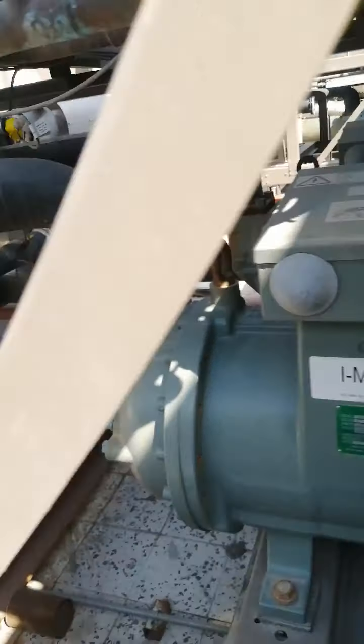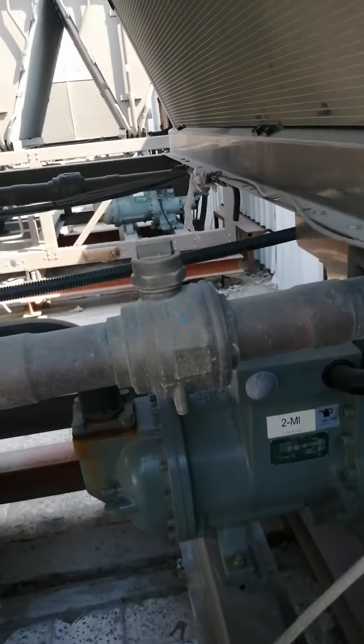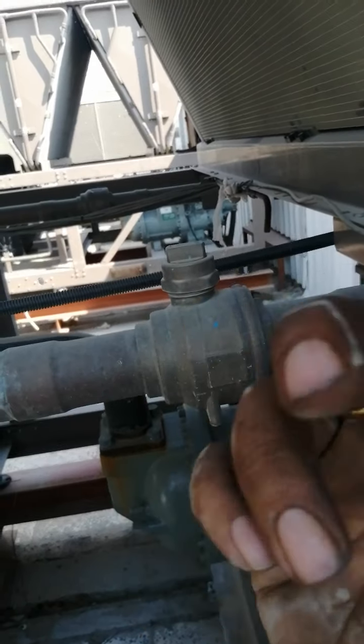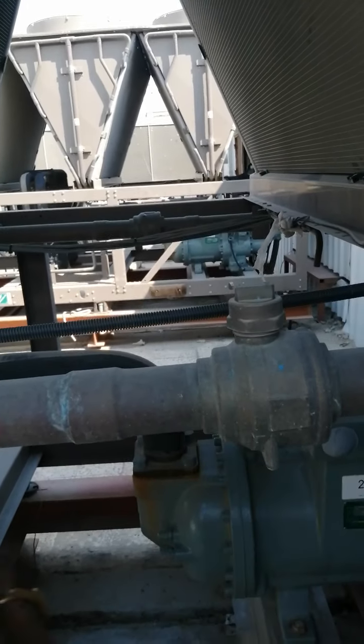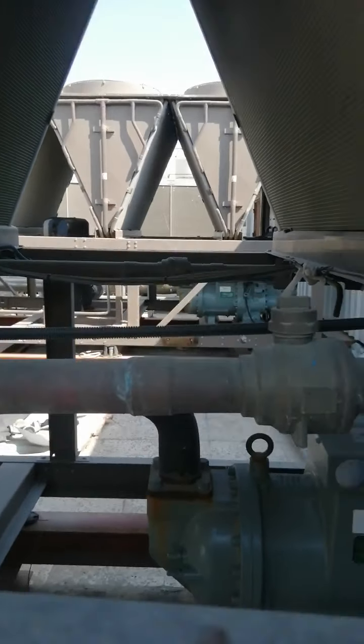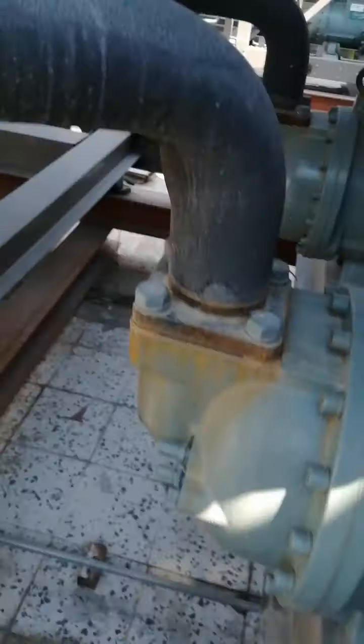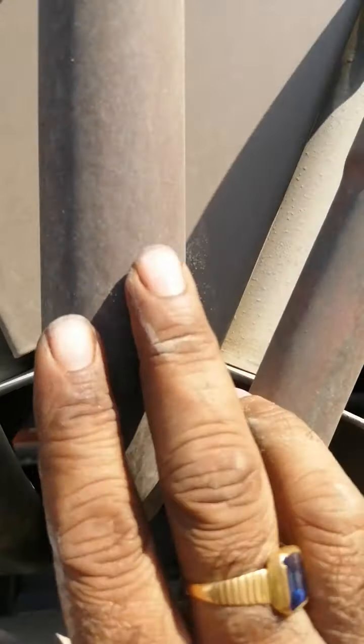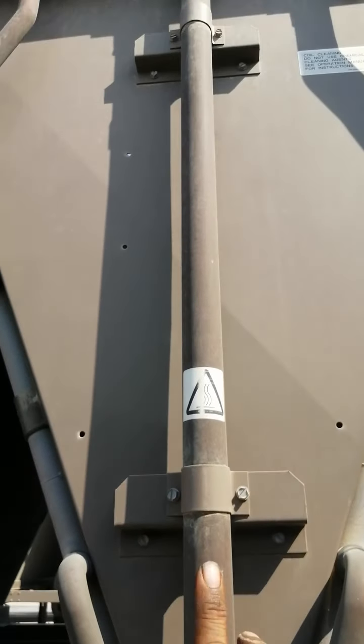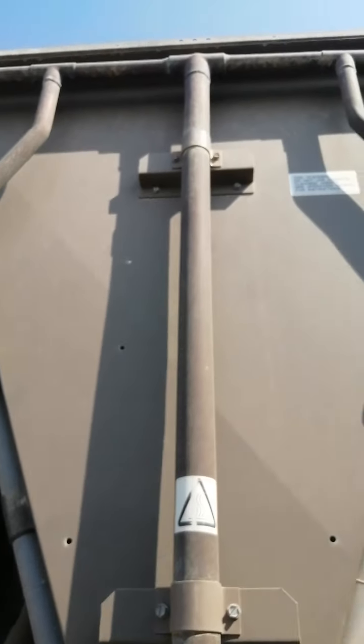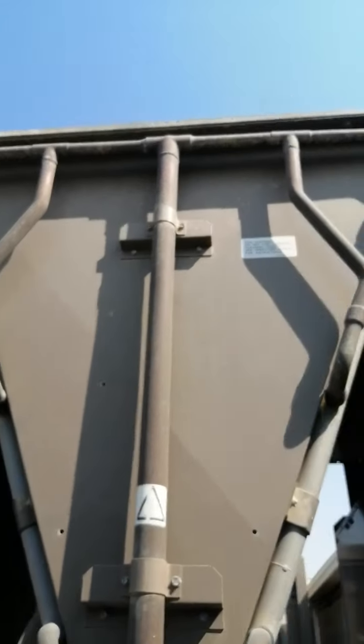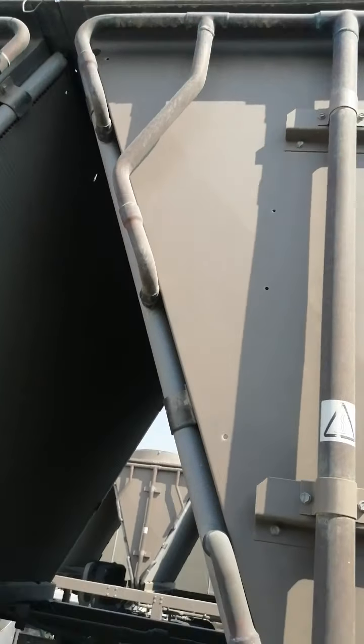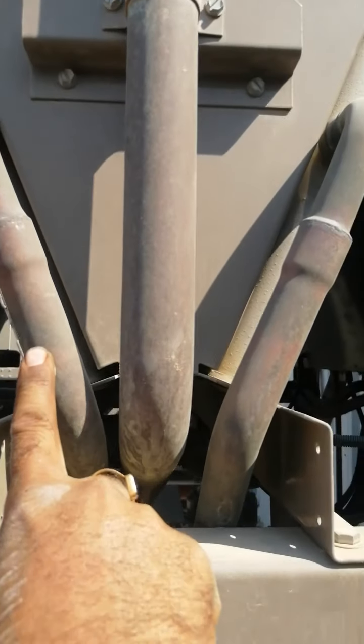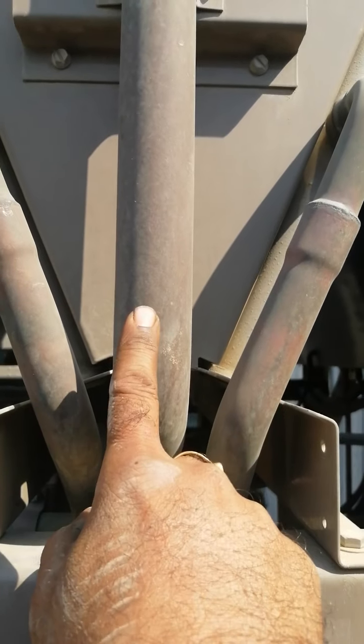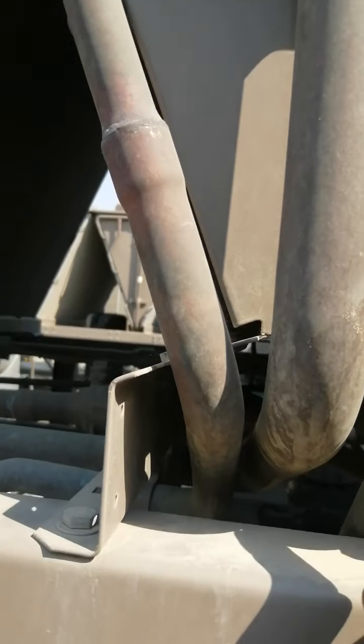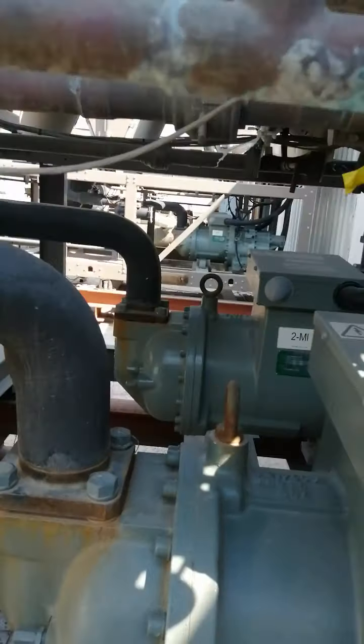This is the discharge shut-off valve. This is the discharge shut-off valve. If you want to work on the condenser, then you shut this off. And this is the discharge line. This discharge line is going to the condenser. Okay, as you see, then it divides into two ports and comes from two ports. This is liquid line and this is liquid line. This is our discharge line. Okay, this discharge line now comes here.